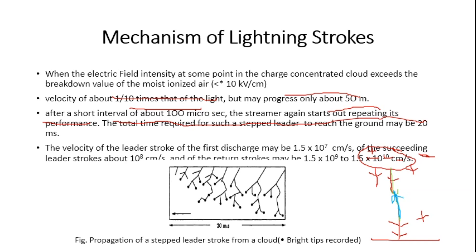The velocity of the leader stroke for the first discharge is around 1.5 × 10^7 cm/s, and succeeding leaders have stroke velocities of around 10^8 cm/s. The return stroke has a velocity ranging from 1.5 × 10^9 to 1.5 × 10^10 cm/s. So there is the step leader touching the ground and a return path going back up.